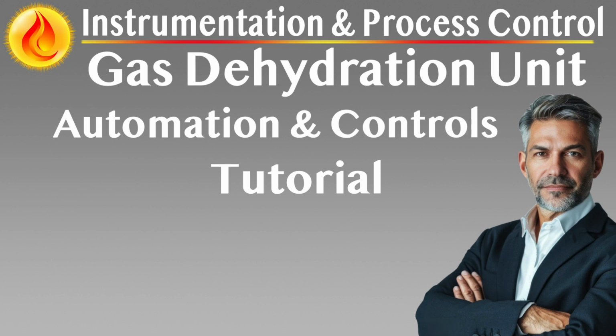Diagnostic and analytic support. Online water dew point analyzers, preferably cooled surface or aluminum oxide types, are integrated with DCS. Instruments support HART communication for advanced diagnostics and calibration. Commissioning and functional verification. All instrumentation loops must be verified for continuity and integrity of wiring and signal path, calibration across expected process range, functional response under simulated trip and alarm conditions, and proper interlock and permissive operation per control narrative.